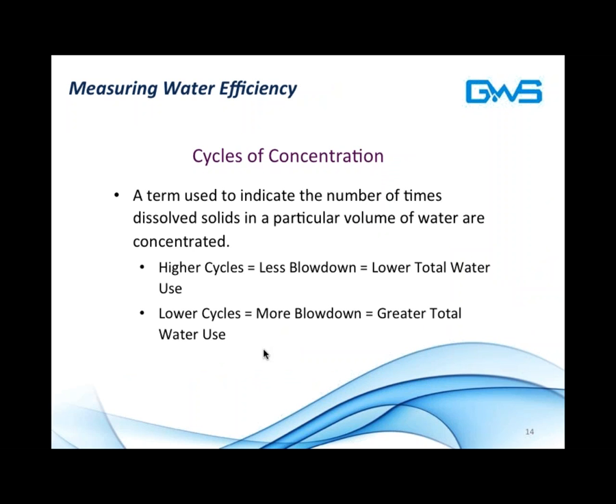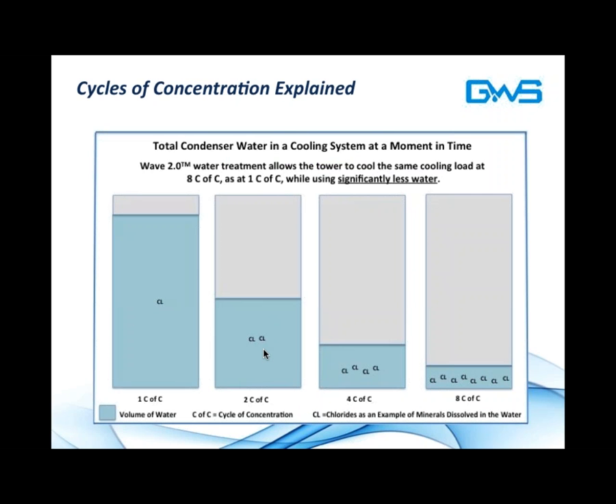Let's just talk a little bit about what cycles of concentration are for those of you that don't know. It's simply a term used to indicate the number of times dissolved solids in a particular volume of water are concentrated. So when you run a tower at higher cycles of concentration, you use less blowdown water, and there's less total water use. If you run lower cycles of concentration, which is to say simply makeup water passes through the tower one time before you throw it down the drain, you're going to use significantly more water. This is a chart that explains what that might look like.